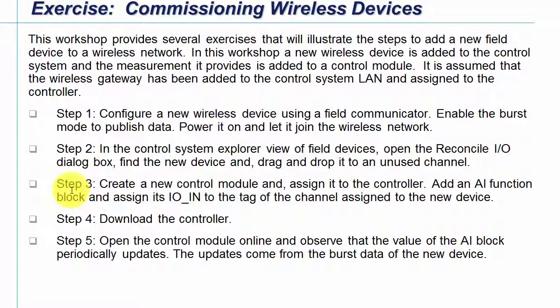We'll create a control module and then assign that measurement from the wireless device to a block within the module, and download the controller. We'll then open the module we created and show how the value from the wireless device is being periodically updated.